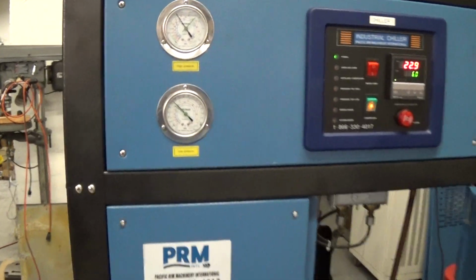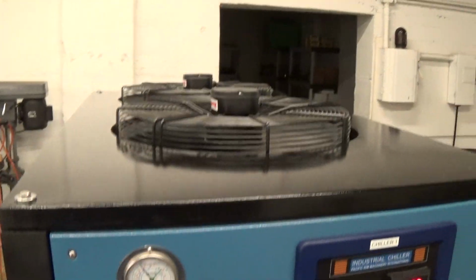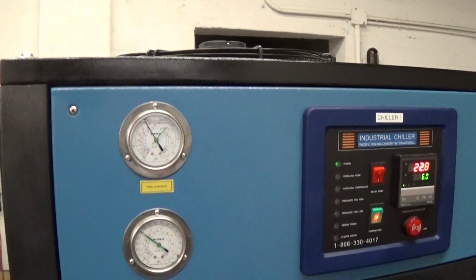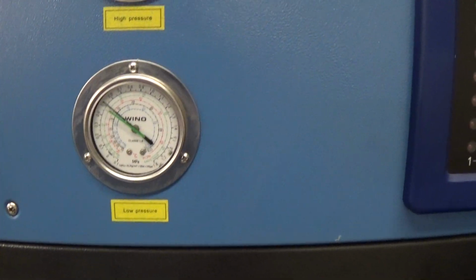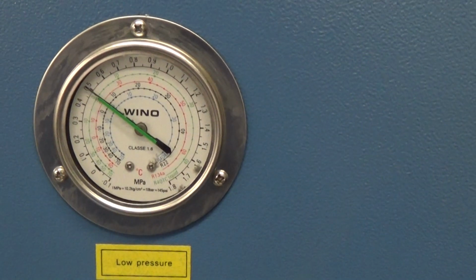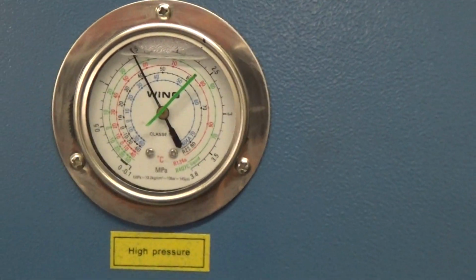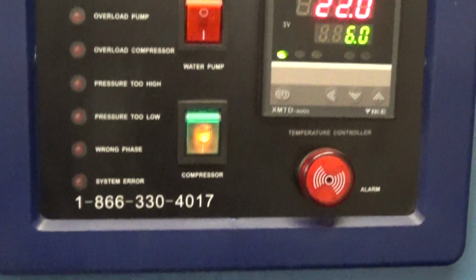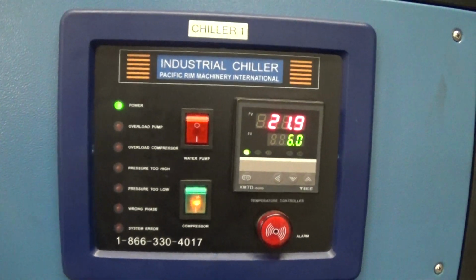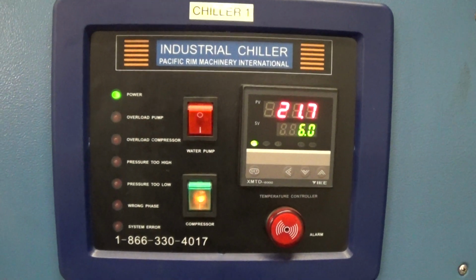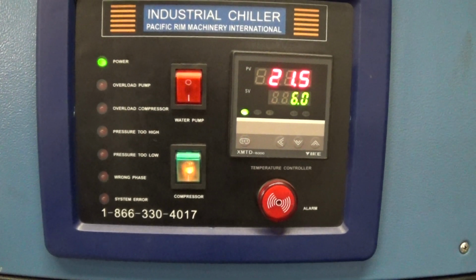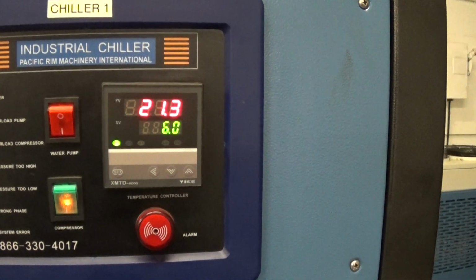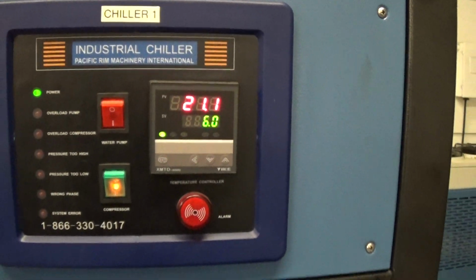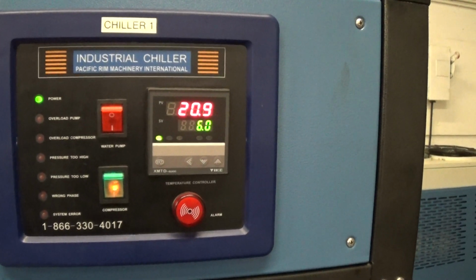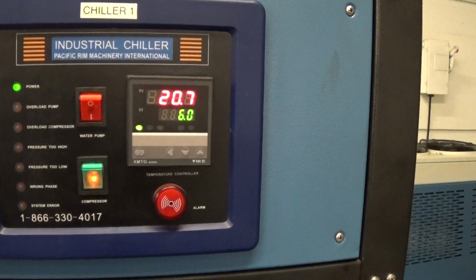We've run it for several days, gone through a few things, touched up the top panel, which had some scratches on it, and repainted it. This is our low pressure refrigeration gauge. This is our high pressure refrigeration gauge. We've checked the charge, we've checked the superheat, and it's a strong running, good industrial indoor chiller. It's not weatherproof to run outdoors. As you can see, we don't have much load. It's just the volume of the glycol in our tank and loop that's going to chill down fairly quickly here.